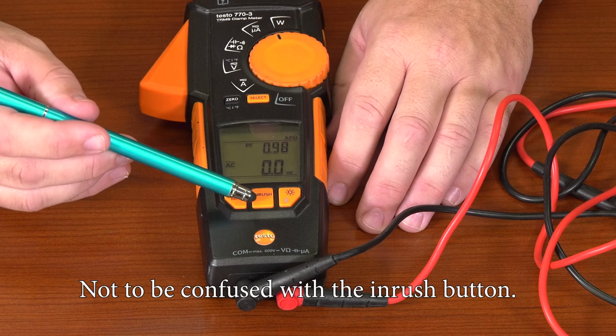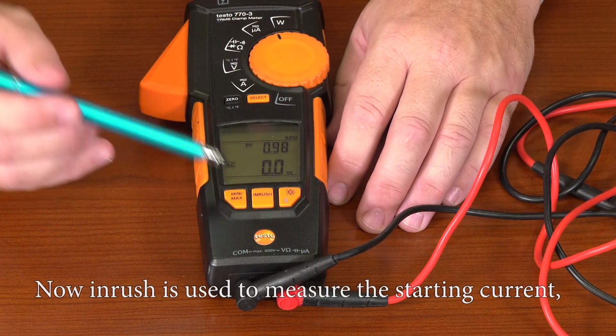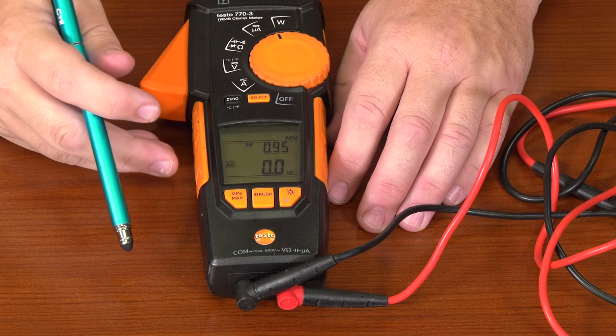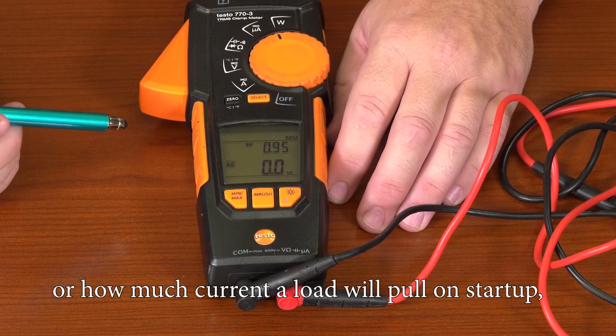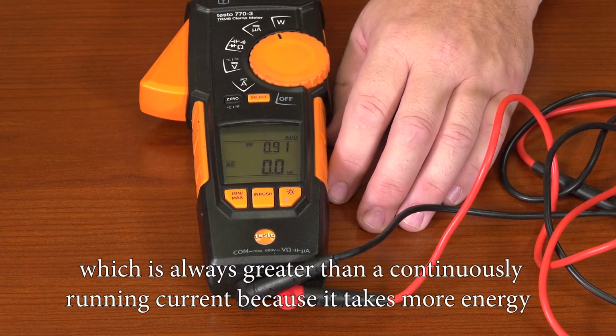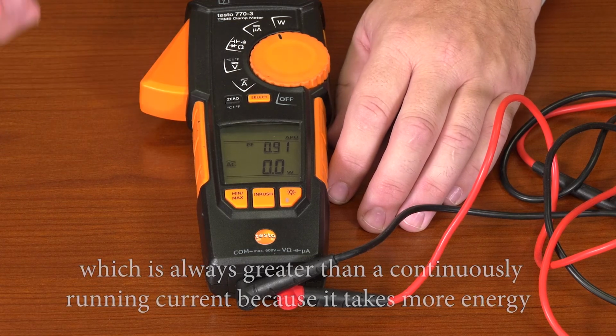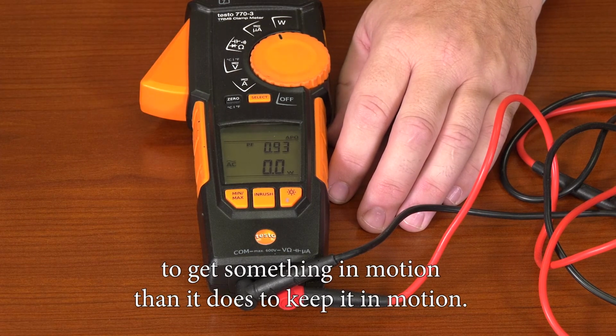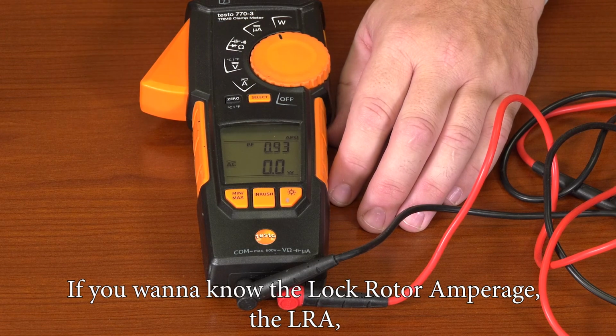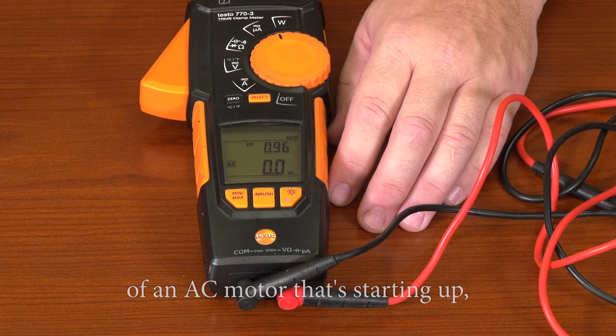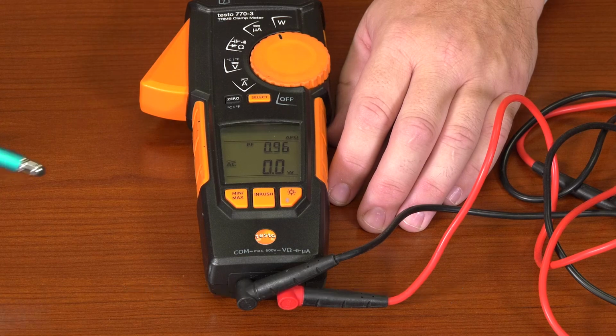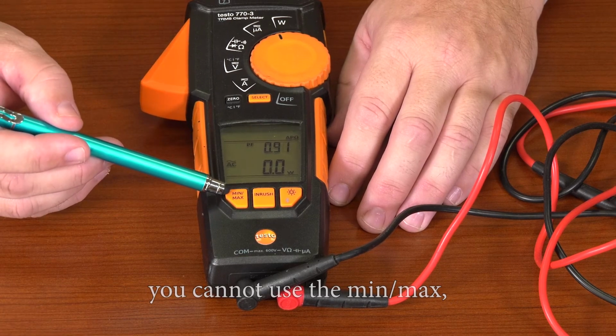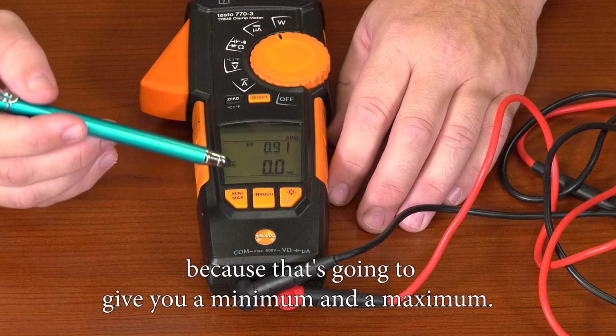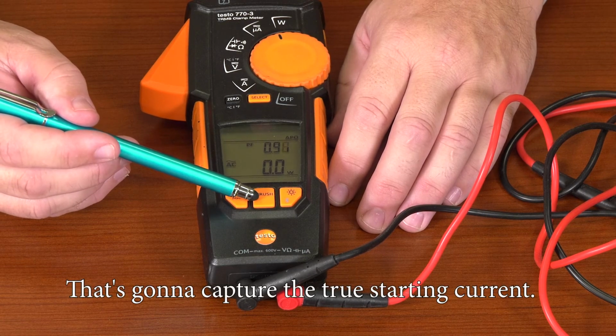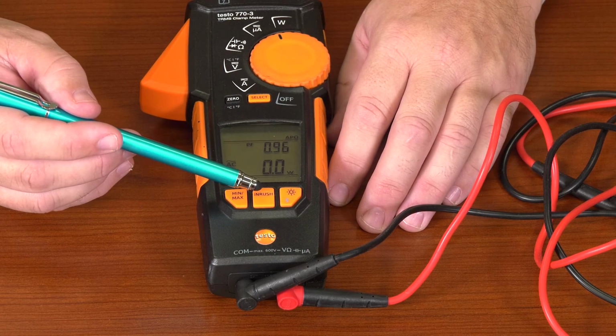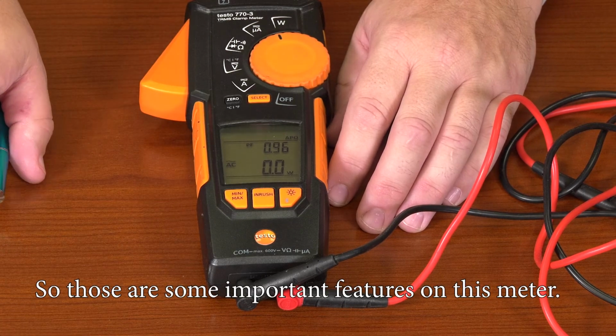Not to be confused with the inrush button. Now inrush is used to measure the starting current, or how much current a load will pull on startup, which is always greater than continuously running current, because it takes more energy to get something in motion than it does to keep it in motion. If you want to know the lock rotor amperage, the LRA, of an AC motor that's starting up, you cannot use the min-max because that's going to give you a minimum and a maximum. You need to use the inrush. That's going to capture the true starting current. So those are some important features on this meter.